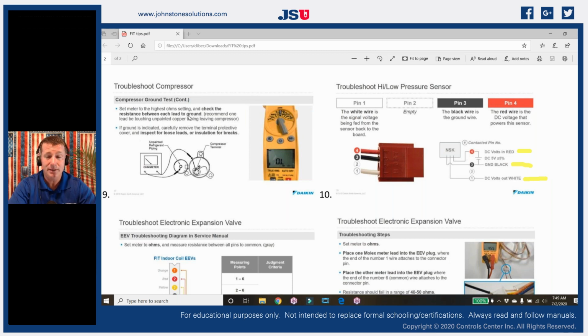So for any brand, you can check those pressure transducers if you think that you're having an issue with one, simply by measuring the voltage that's coming out of them, or by unplugging it and checking the resistance that comes across it. It's really simple technology when you look at it from that perspective, because even our actual temperature sensors, they're just changing the resistance so that we can change the voltage.